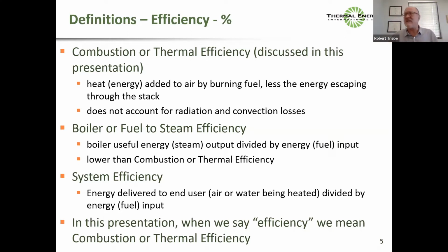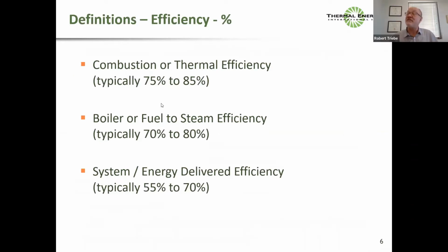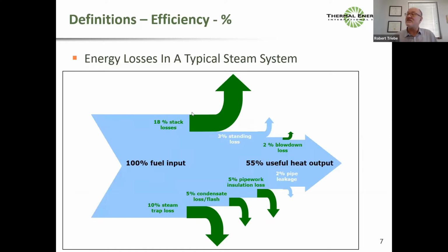And then there's a greater concept of a system efficiency, which is like how much energy actually gets to the end user, how much energy reaches that bedroom in the hospital or reaches that process heat exchanger in the field. That's more like a system efficiency concept. So typically in this presentation, when I'm talking about efficiency, I mean combustion efficiency. Combustion efficiency is typically 75 to 85%. Boiler or fuel to steam efficiency, typically 70 to 80. The delivered efficiency is typically 55 to 70, quite low. And that's a result of this.